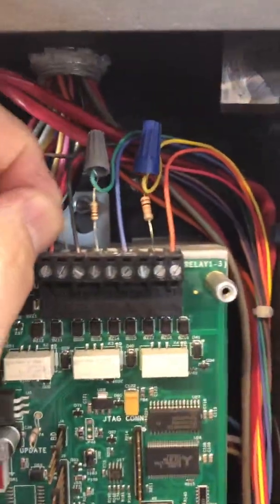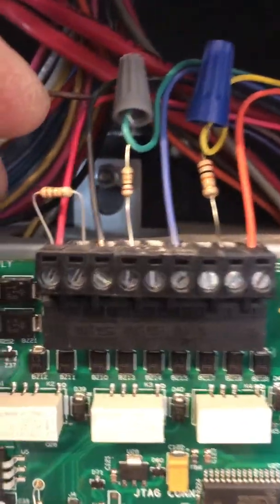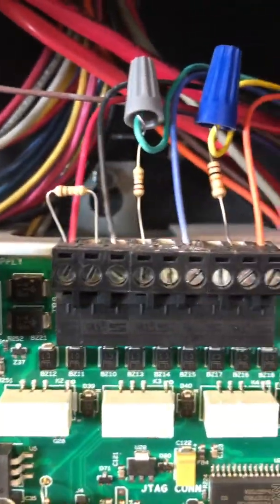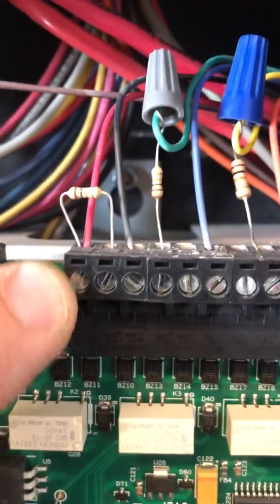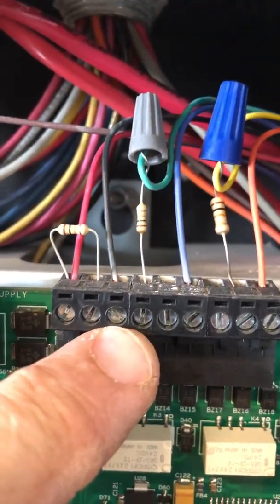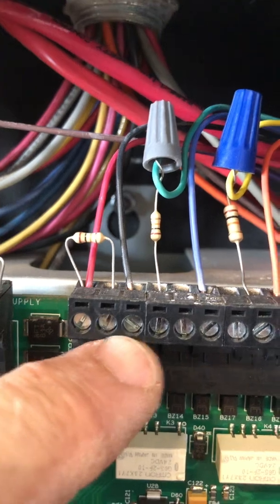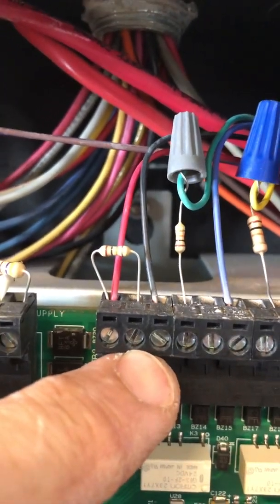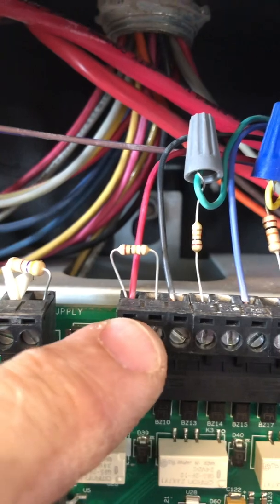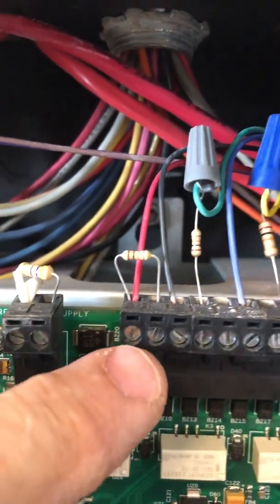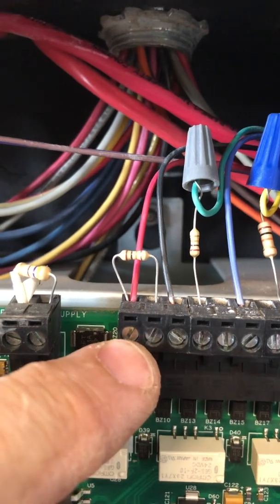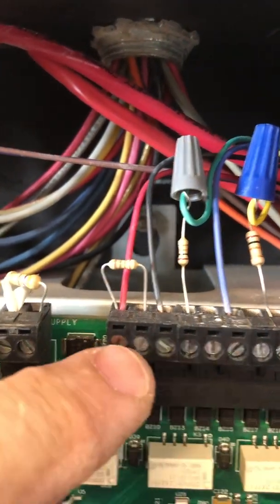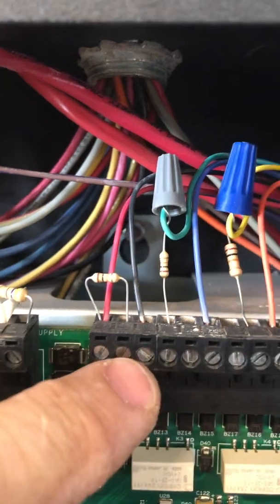First thing you'll notice is the resistor for the alarm goes from normally open to normally closed in the center, and then the normally closed is shorted with the common. So basically this is gonna supervise the alarm circuit if somebody removes this plug, but essentially you have your resistor from the end of the line going from red to black.